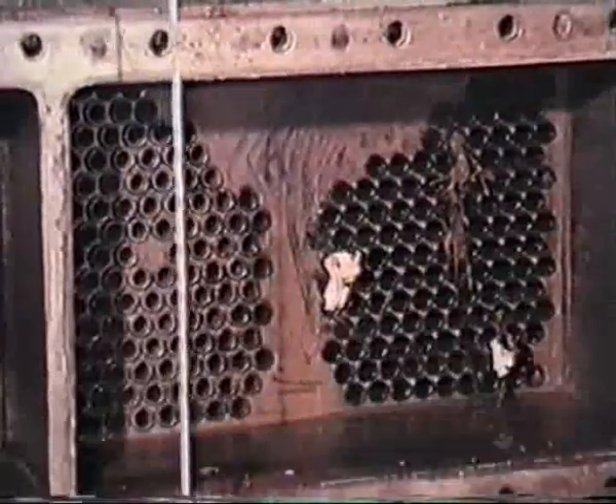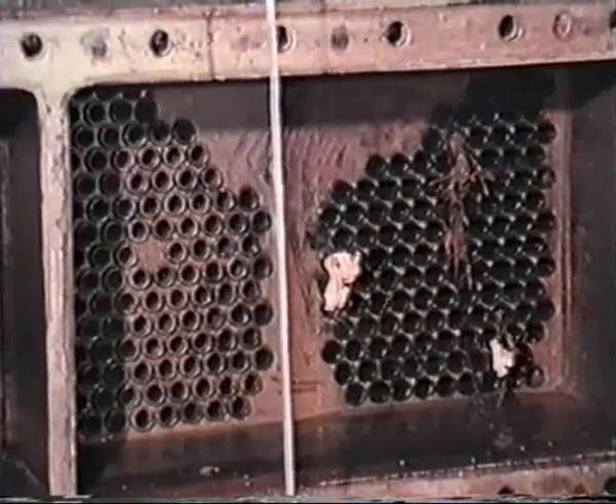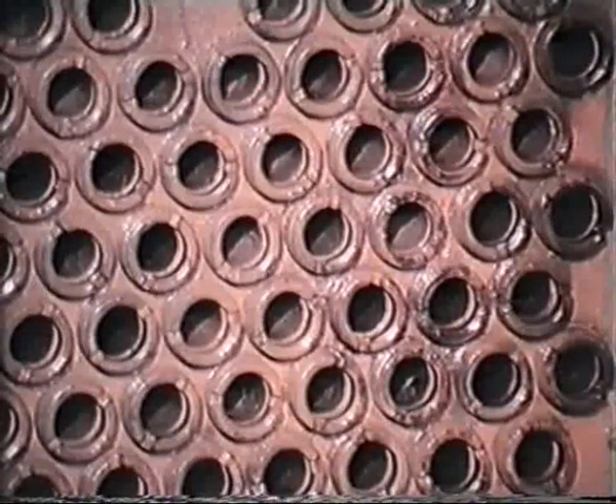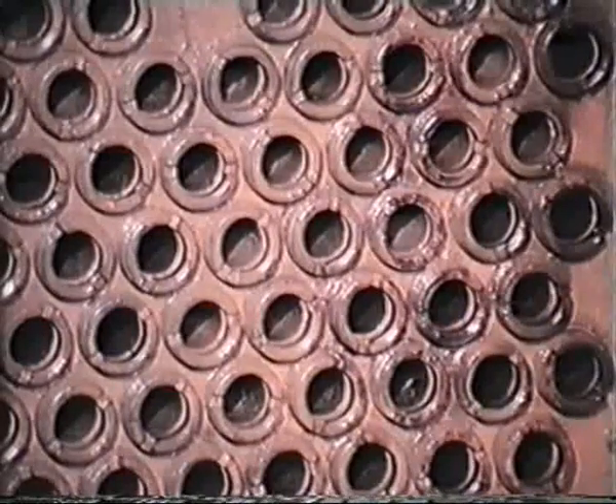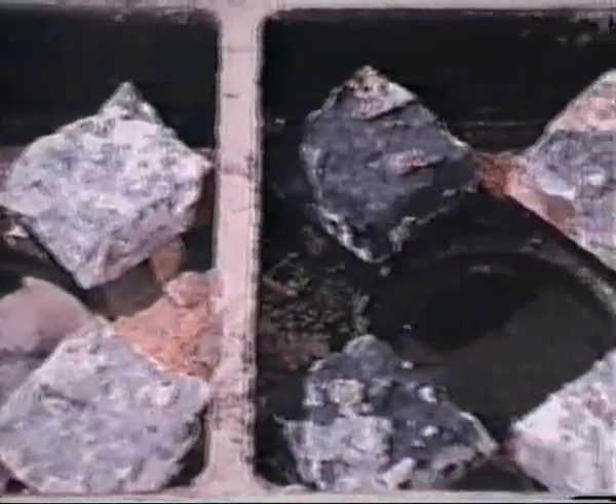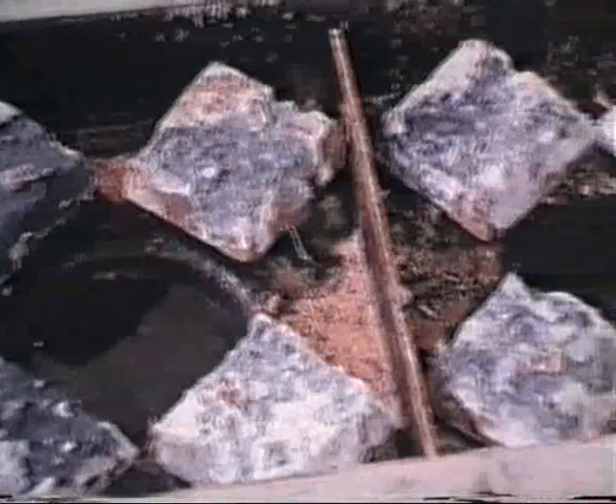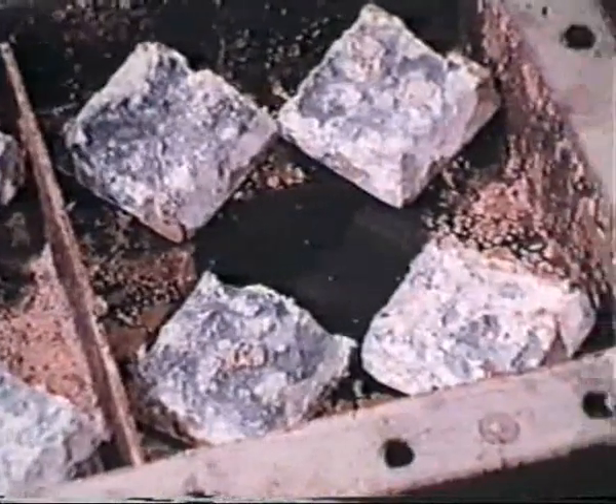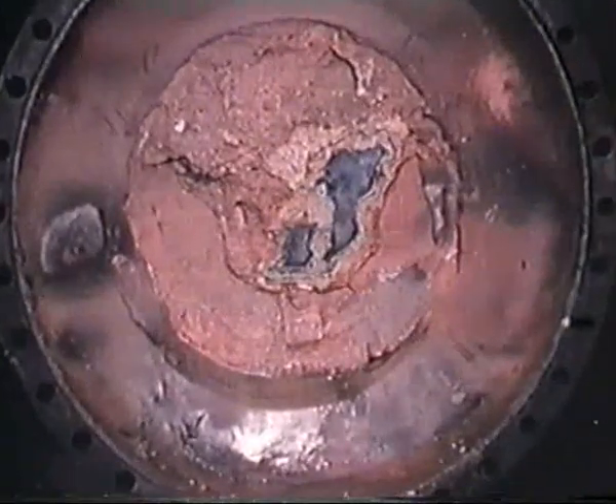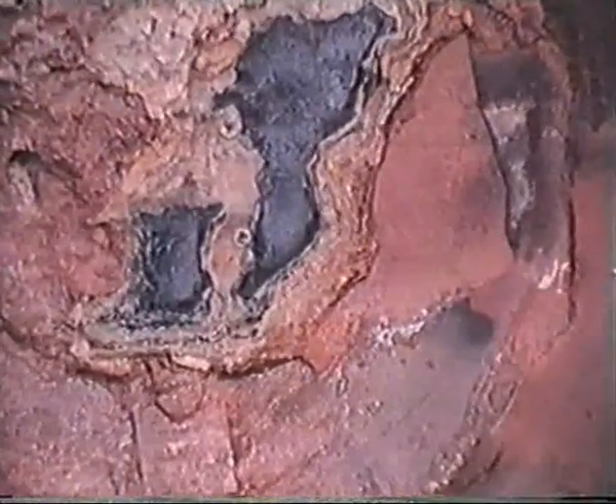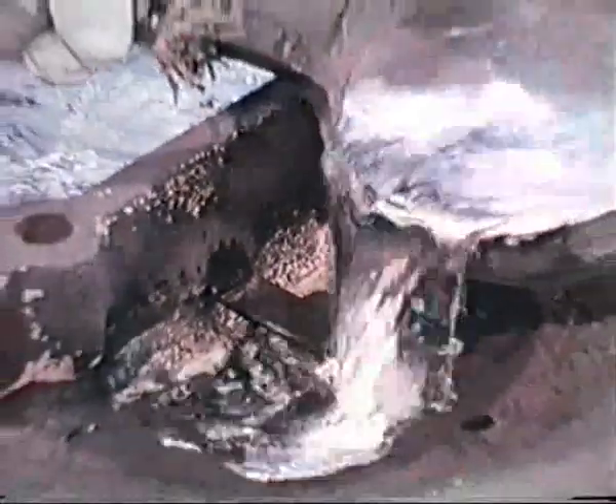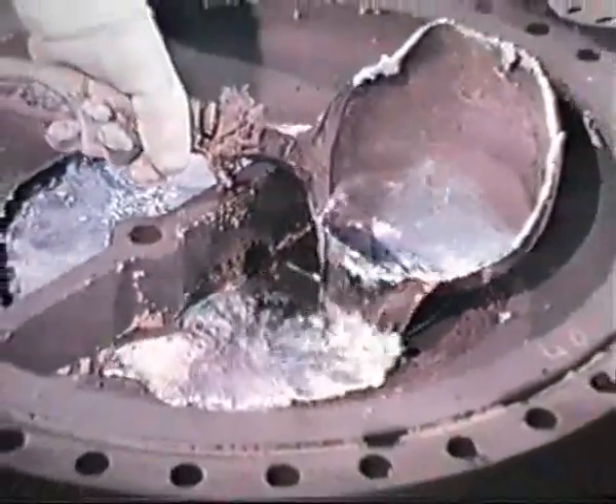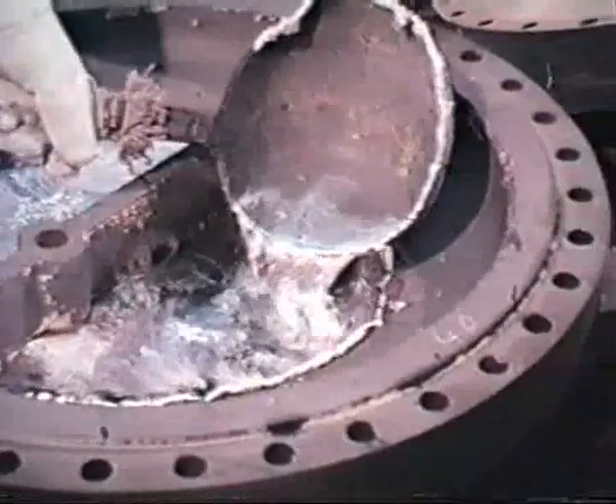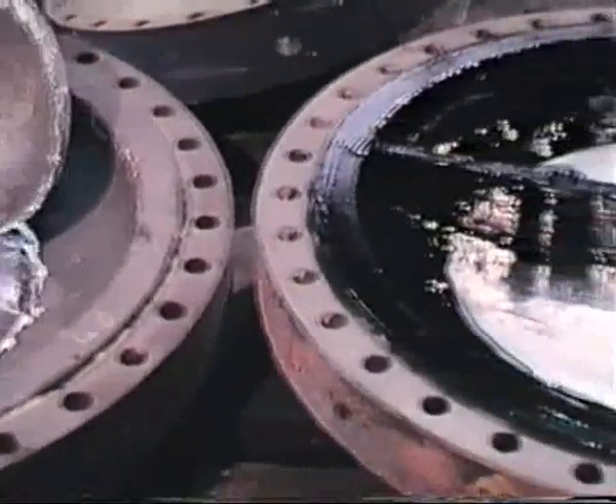The steel shell of a heat exchanger not only has to withstand normal corrosion, but also aggressive bimetallic corrosion from coupling with the copper tubes. This is overcome by placing the steel in direct contact with zinc, lower in the electrochemical series, so that both steel and copper are protected at the expense of the zinc. Similarly, on end plates, the zinc is sacrificial and replaced at normal maintenance periods. Where possible, further protection comes from an insulating coat of paint.